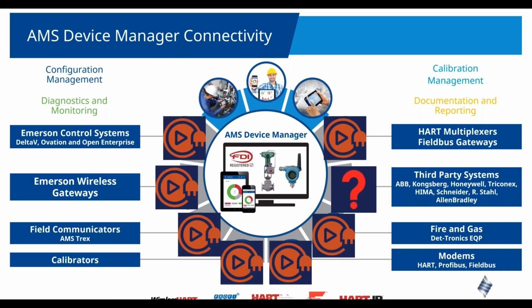But what do you do about the bad guys out there, the PLCs, the remote IOs? How do I connect into those, when I don't understand the language? Even if I have a full plant of DeltaV, you always have some skids with ABB or Allen Bradley remote IOs, or Kongsberg, or maybe a HIMA system for your safety, a remote IO from Stahl. I need to be able to get the information from the instruments connected to those PLCs as well. That's where Softing comes in handy.